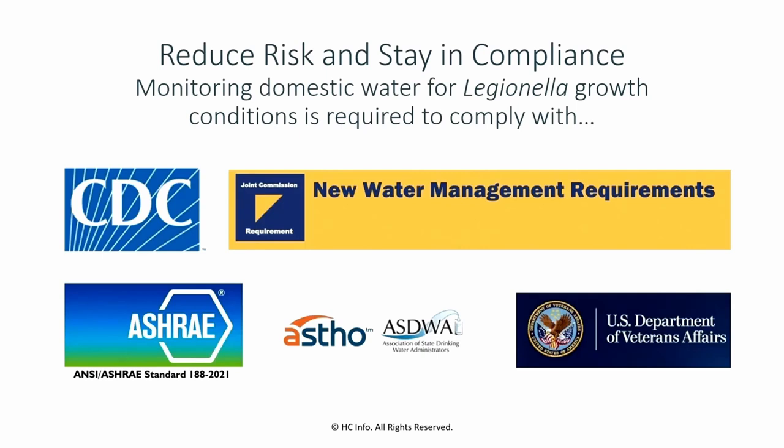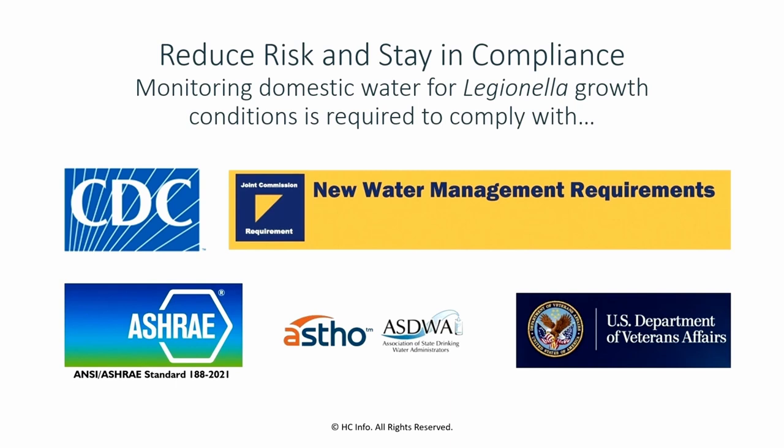Some of the documents that are requiring it: VHA Directive 1061, the new standard by Joint Commission that hospitals accredited by Joint Commission have to follow. The Association of State Drinking Water Administrators, along with the Association of State and Territorial Health Officials, came out with a document specifically on monitoring water quality. It's in ASHRAE 188, and the CDC has a document on monitoring water quality — in their water management plan checklist, they have a list of parameters to consider testing for. So all of these documents require it. Why does it make sense from a risk reduction standpoint to test not just for Legionella, but for conditions that can affect Legionella?